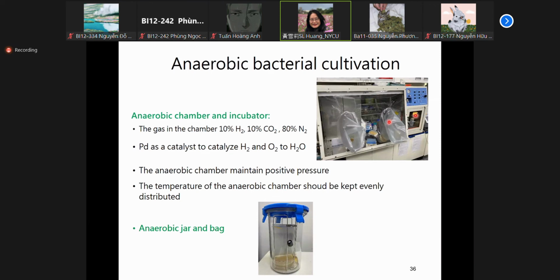Okay, there's like a two-way process of getting to these anaerobic conditions. The anaerobic chamber will maintain positive pressure to prevent the oxygen from the environment getting into the system. And we also want to make sure the temperature is kept evenly distributed, because after the inoculation, we still use this chamber as an incubator. We leave our plates or tubes inside the chamber, so we hope that the temperature is well controlled.